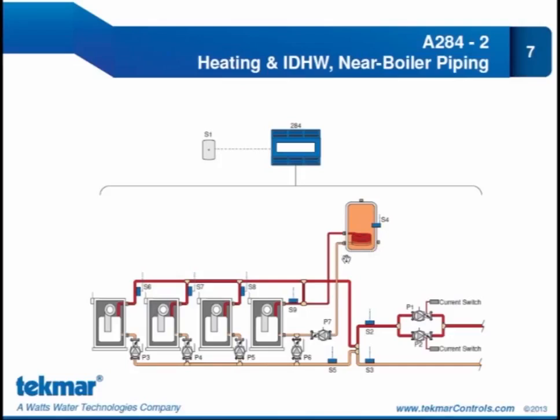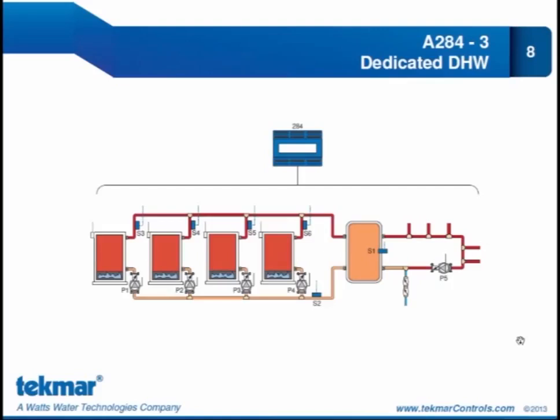So we have IDHW here with near boiler piping, and the near boiler piping must be off the 4th boiler. Again, we have dual primary pumps. This time we are proving flow with current switches instead of the flow sensor. So we do have that flexibility. You don't have to use the flow sensor to prove flow. You can use any type of flow proving device. Our third application shows dedicated domestic hot water, which we refer to now as DHW.